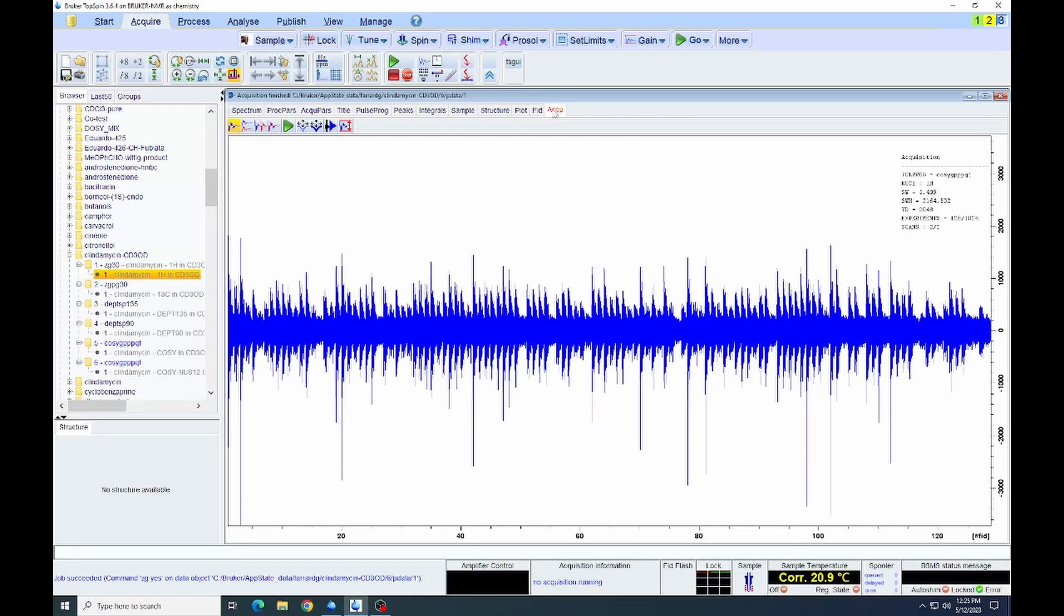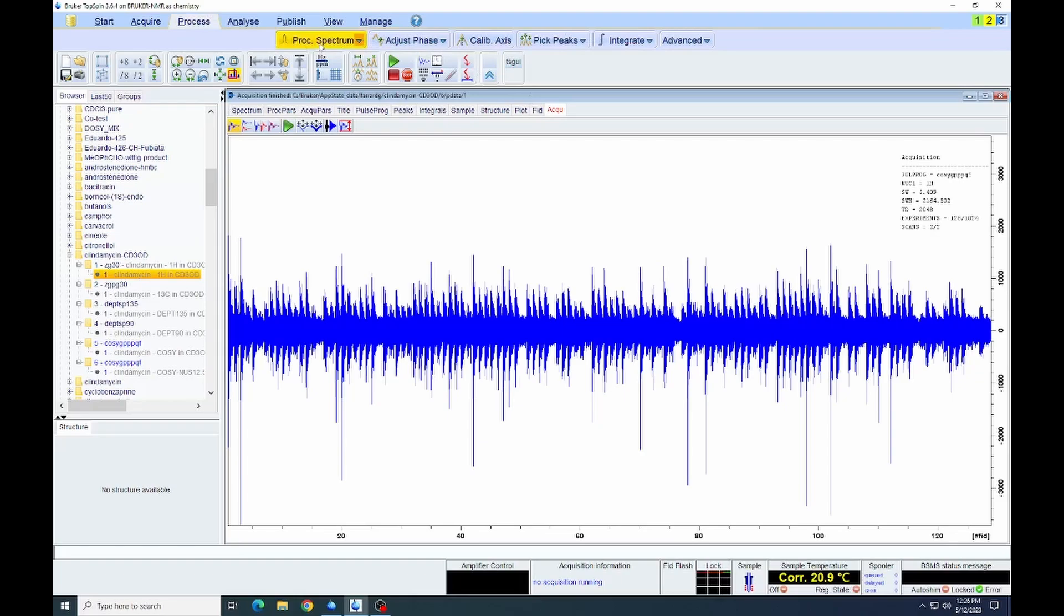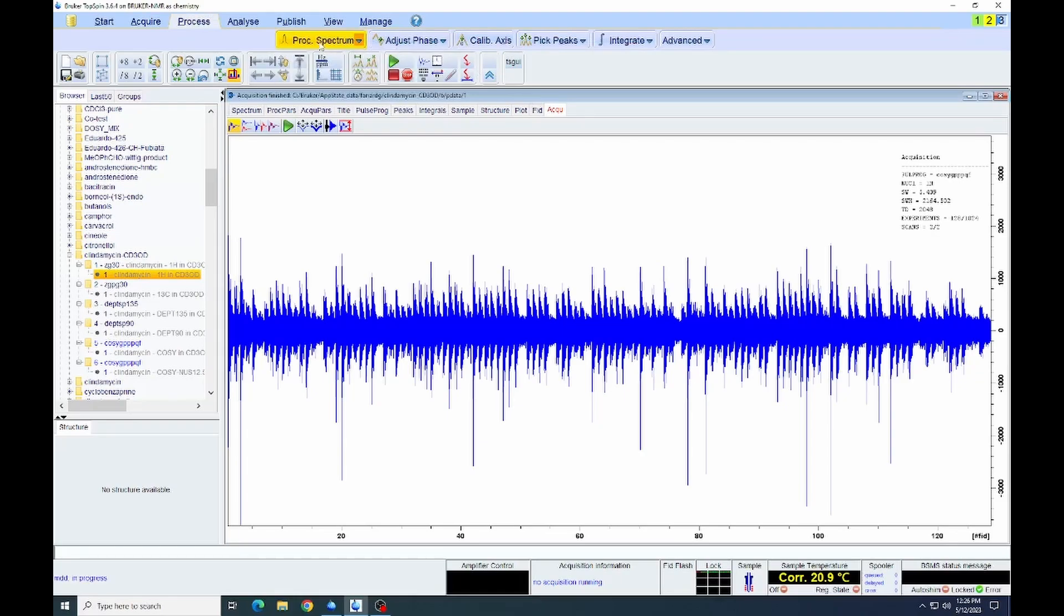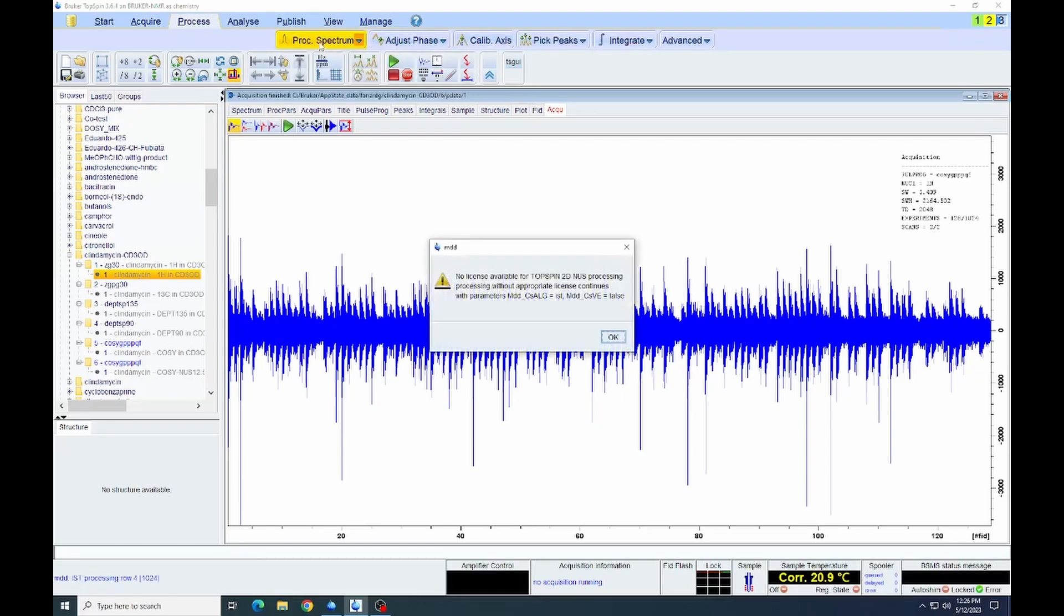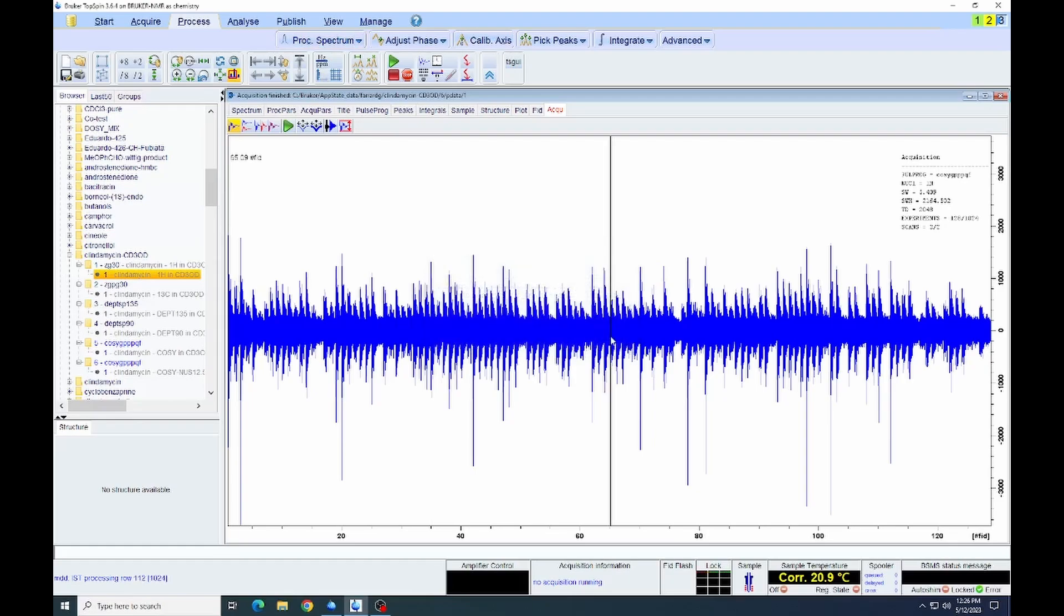So at this point, the acquisition is completed. So we're going to process the spectrum. When we do, we do get a pop-up message that we don't have a license. We click OK and it will continue to process it anyway. It just doesn't use a special NUS processing package that's available. You can see the processing here is a bit time consuming, although not excessively so. Certainly it would take longer to acquire the extra increments. The processing is a little longer, but we do pay a small price at the back end for a big savings at the front end for the acquisition.